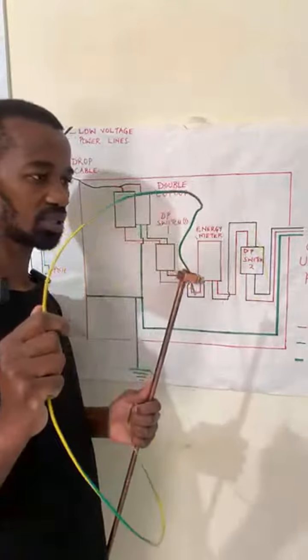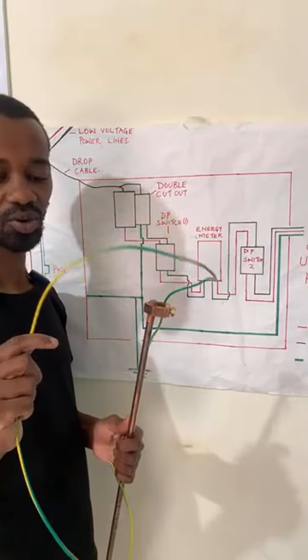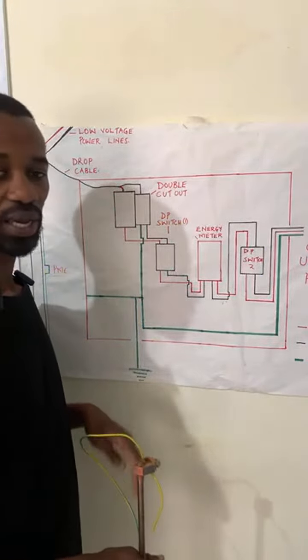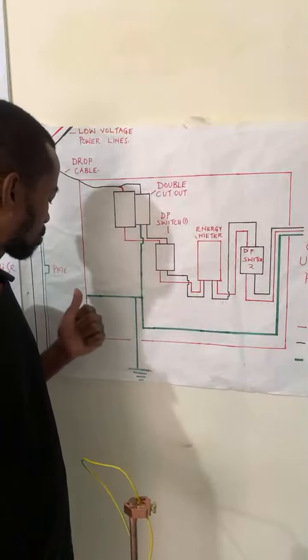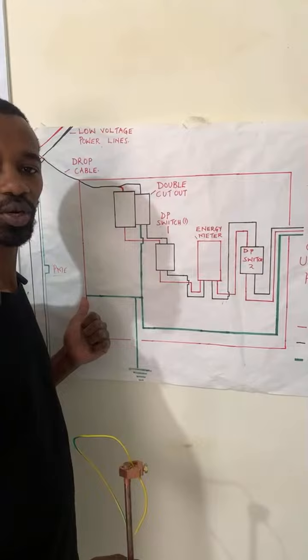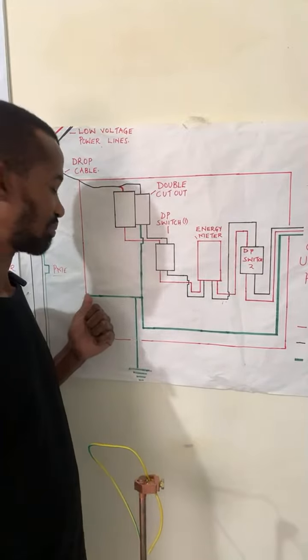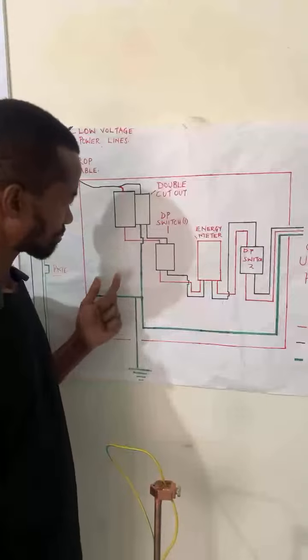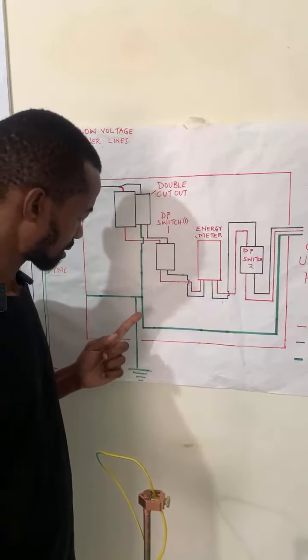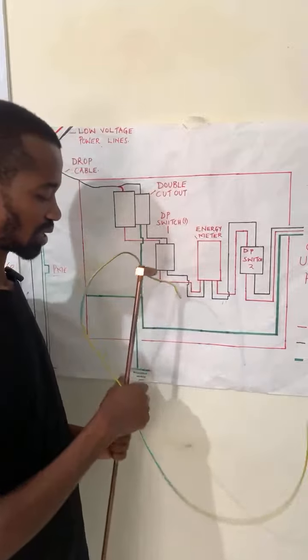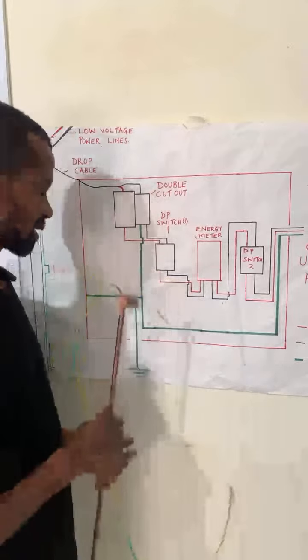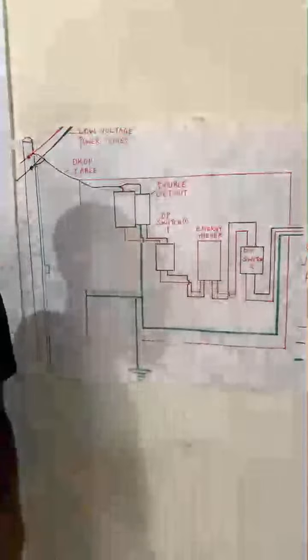So this cable, this is not the standard size. I've just used this because of the color so that we are able to understand each other. So it also has to be consistent with the cable that is bonding at the meter box. So the meter box cable, the cable dropping from the neutral bonding, as well as the cable going all the way to the earth rod should have the same size, the same as the cable that is going all the way to the consumer unit. So let me know, my top boss, what do you think? What is the size of that cable?